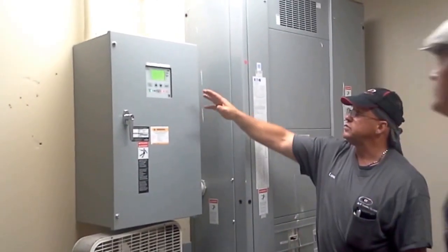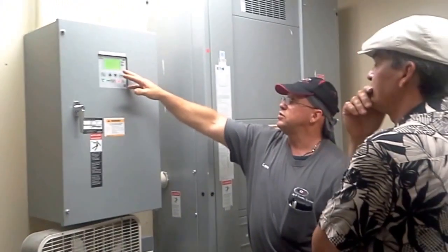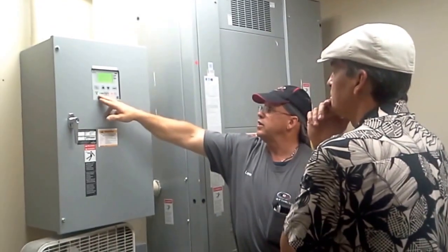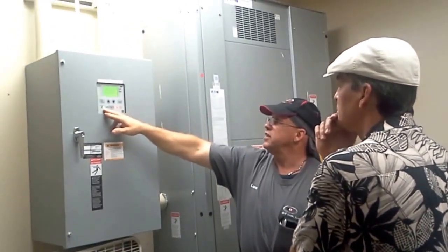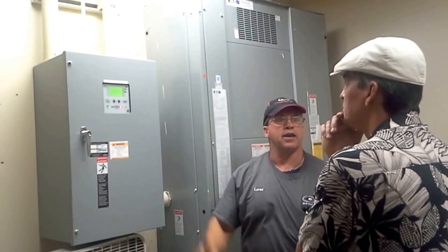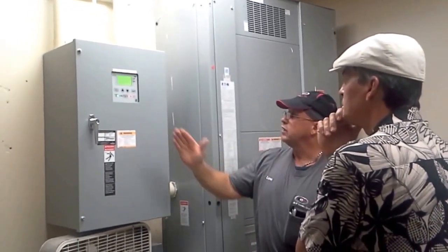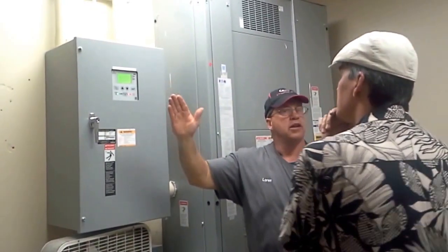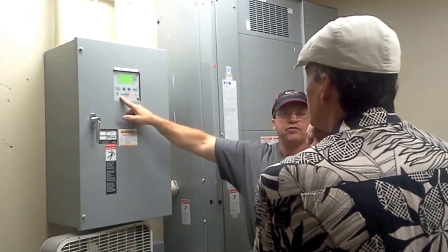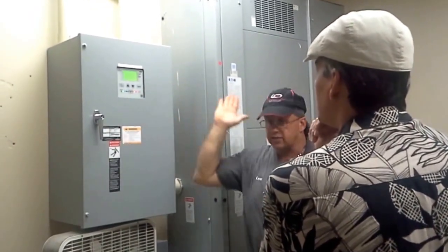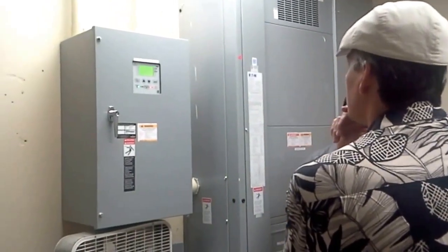Now let's say, per se, right now you lost utility, then even for a second, that light will go off, the light will then come back on, and that will go right back at 10 minutes. It has to be 10 minutes consecutive. And I get the question, well, how about on cool down? As soon as that's on cool down, if that light flickered off, this thing will instantly go back on that generator.